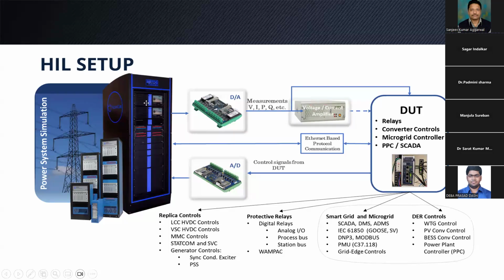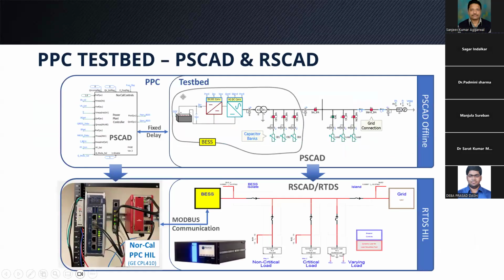The plant which we modeled in PSCAD, now we'll model in RTDS. The software is called RSCAD. The plant is modeled here, and then the device under test will be a physical device. In our case, it will be either a microgrid controller or a PPC. The PPC will be a real PPC, and your model of the plant will be a simulated one. So the inverter is simulated, the grid is simulated, the transformer, everything is simulated. Only the PPC is a physical controller.